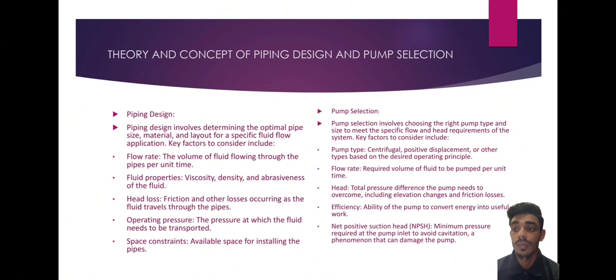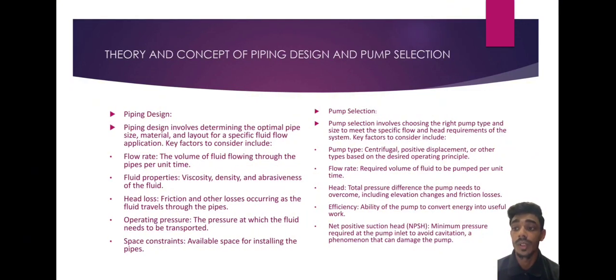Key factors to consider include flow rate, the volume of fluid flowing through the pipes per minute; fluid properties, viscosity, density and abrasiveness of the fluid; head loss, friction and other losses occurring as the fluid travels through the pipe; operating pressure, the pressure at which the fluid needs to be transported; and space constraints, the available space for installing the pipes.